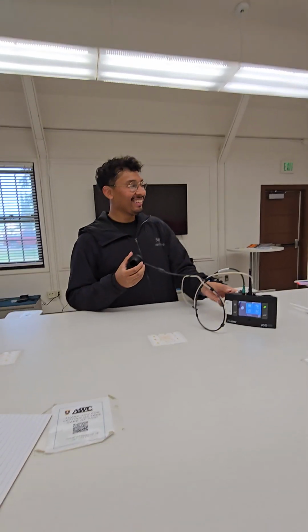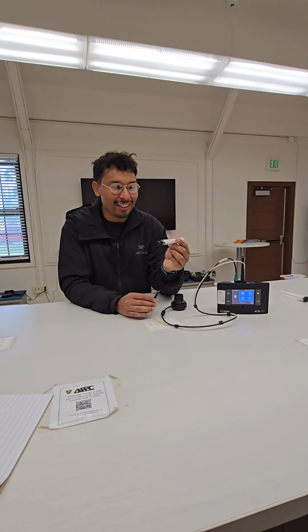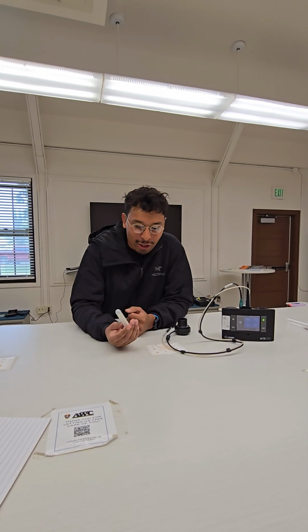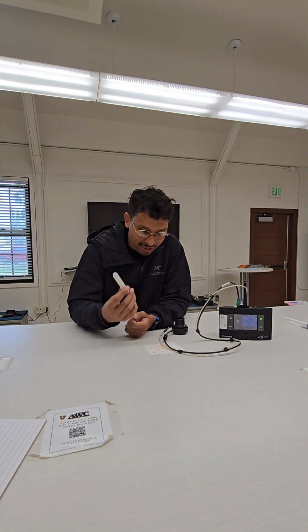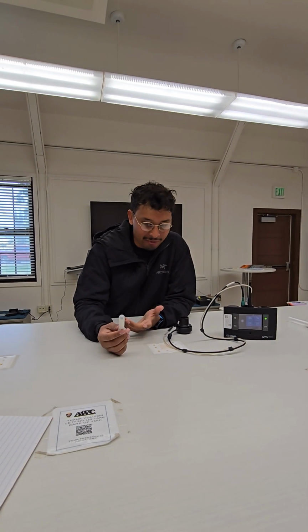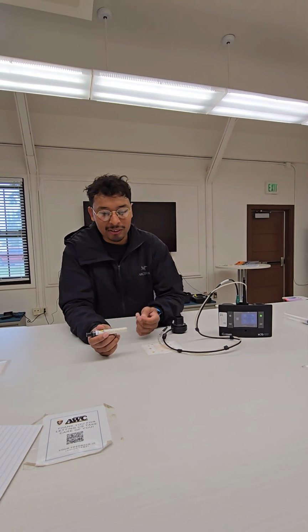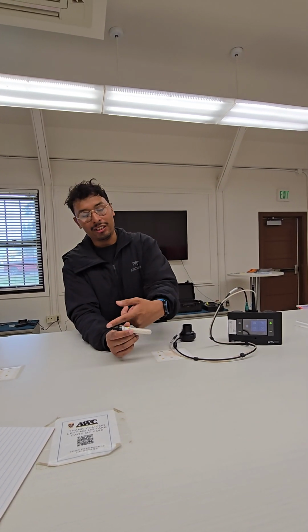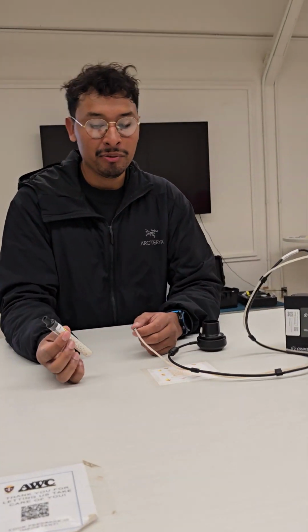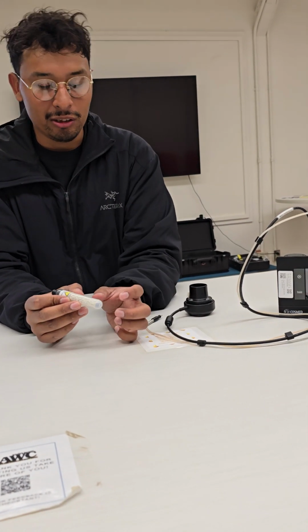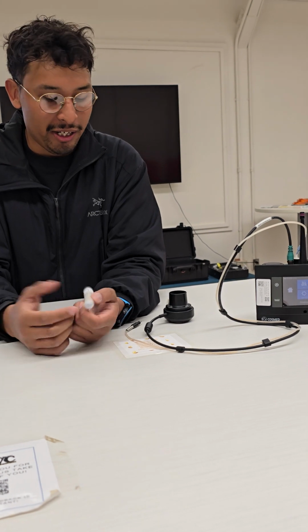Wait, how'd you get that? The scrubber calibration. The scrubbers usually last a year, so you'll have to replace these yearly. Over time, basically all that happens is CO2 or air is being moved into the tube, up the sampling line into the analyzer, and over time, the rocks will start to expire.